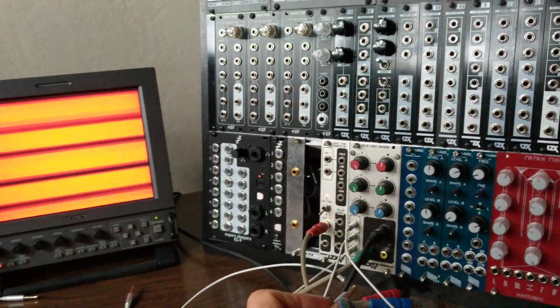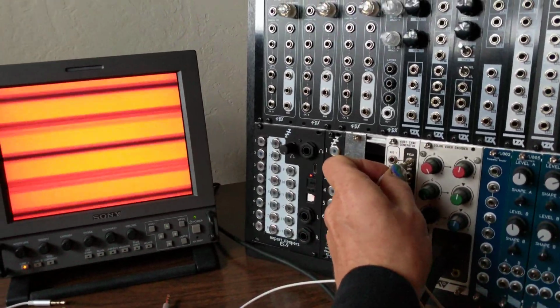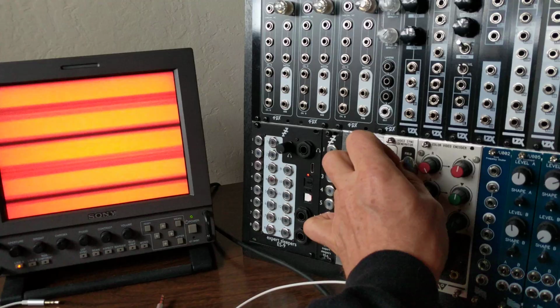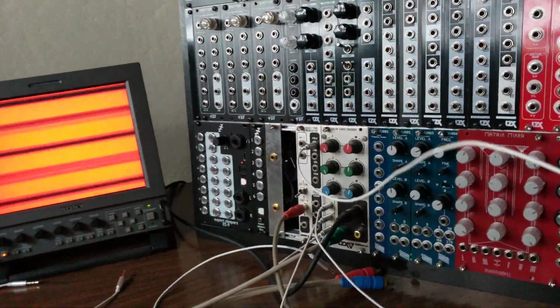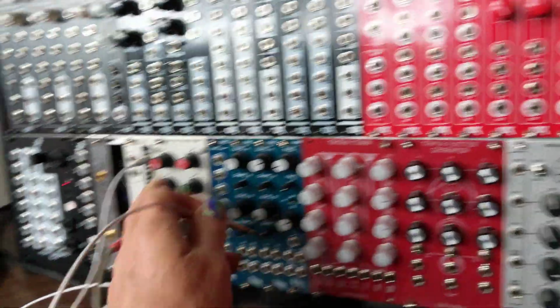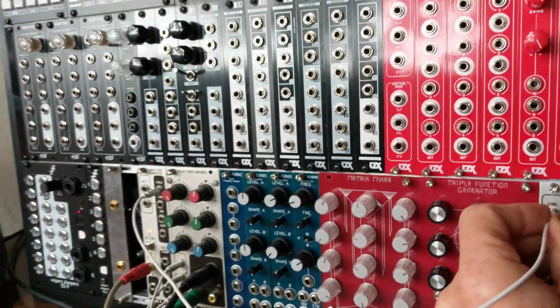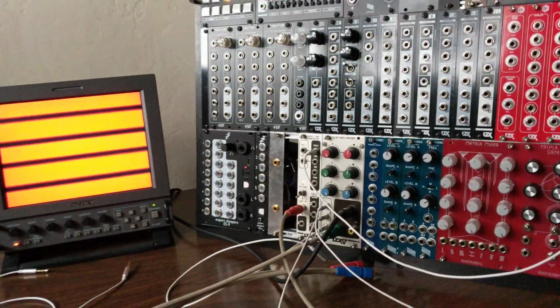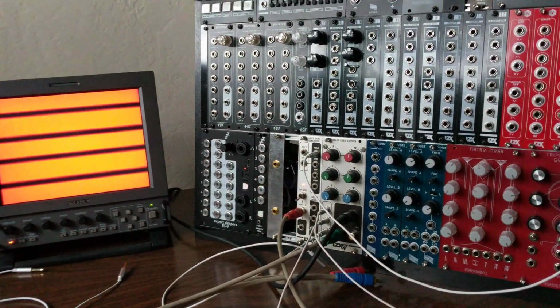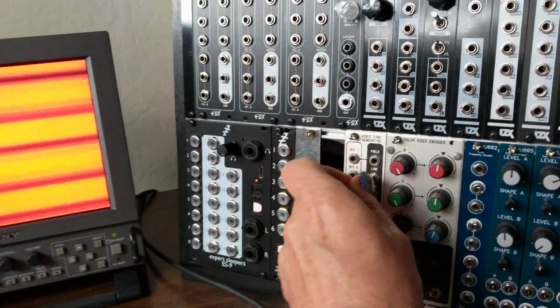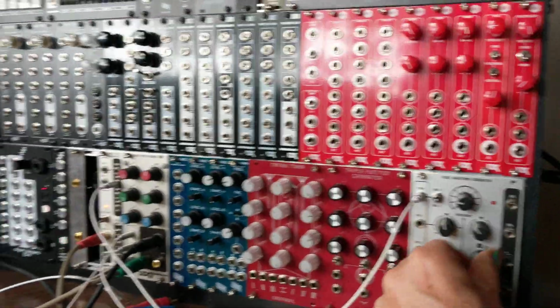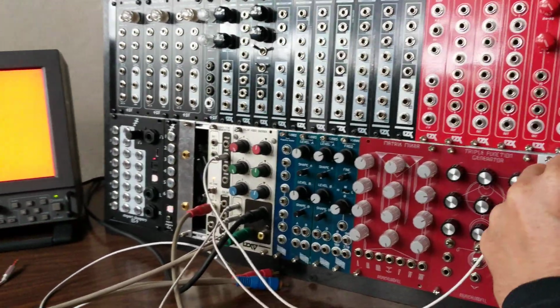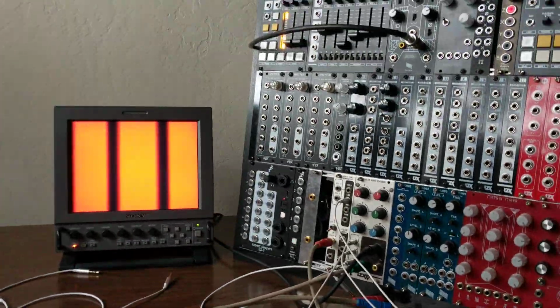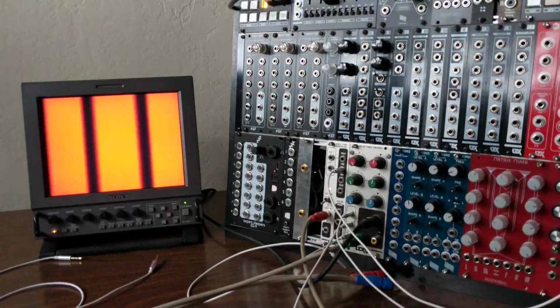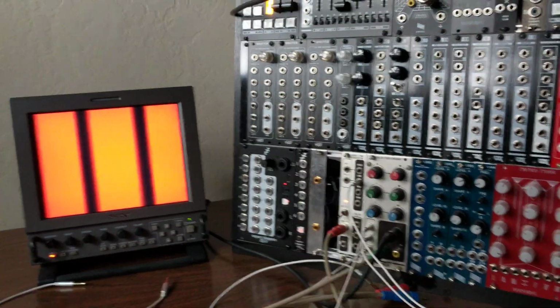So these are horizontal going lines, therefore it's at video sync, sorry, vertical sync rate. So if I take the field out, those lines lock. And then if I take the line out, which is the H-sync, and turn the range up, you can see that the horizontal sync is also working coming out of here.